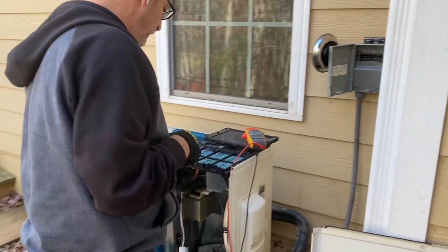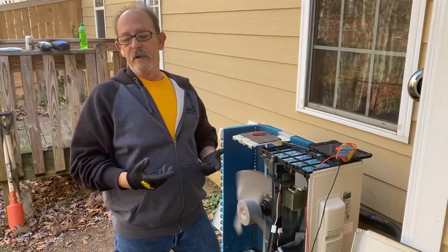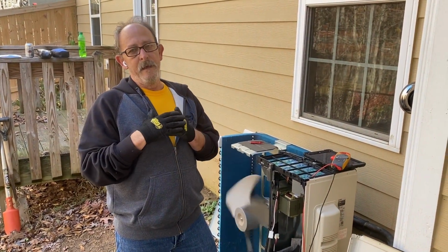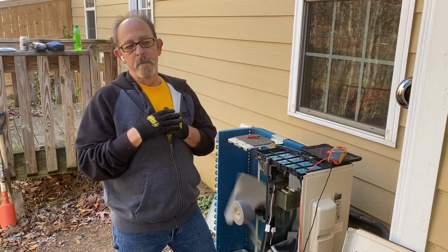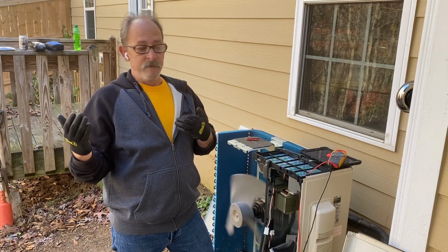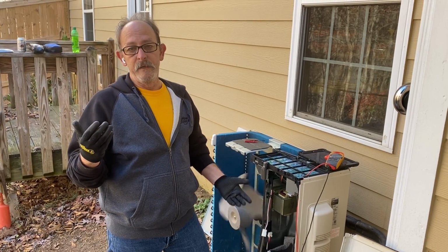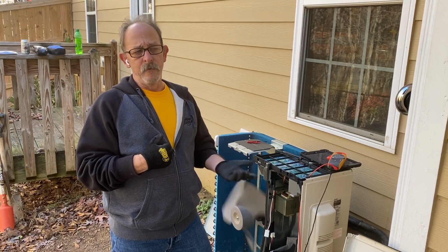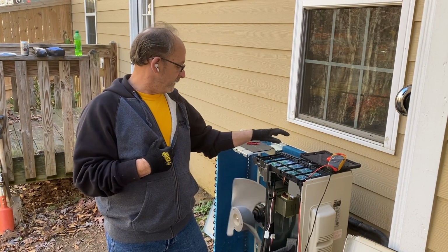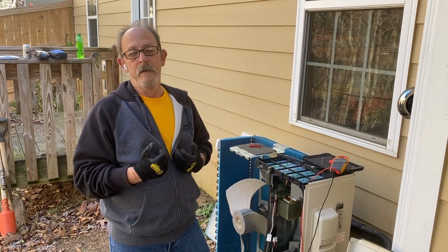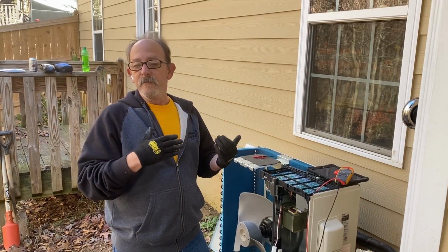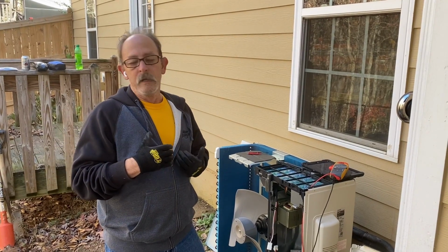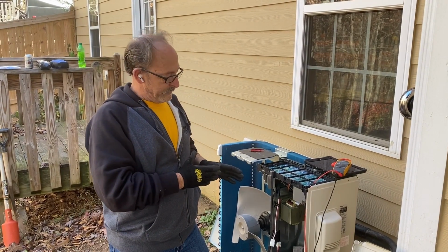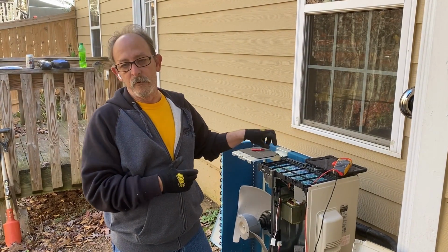In the service manual, you can go to testing the compressor, and it's going to give you a voltage range of what your compressor would be good for. So in this case, it was 49 volts. If I go into the service manual, it'll tell me that from 40 volts to 150 volts or whatever, that's what your compressor should be. That's what your voltage coming from the board should be.